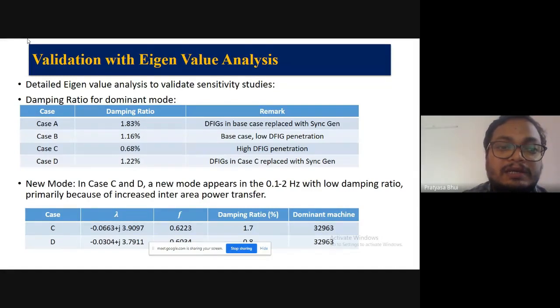In case C we have more renewable generation. So as compared to case B, we can see that the damping ratio has reduced further. Now in case D, you can see that there is improvement in damping ratio because we have replaced the DFIG with synchronous generator. That means an increase in inertia, so it has increased the damping ratio.